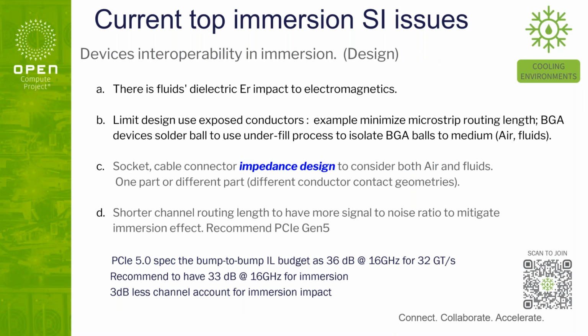This is also by design. We know that immersion has a dielectric constant impact, so impedance design is critical. One way is to tune the immersion impedance and interconnect impedance. Another way is to increase the signal-to-noise ratio, so we have less channel loss to compensate for the reflection loss caused by the liquid. For example, PCIe 5.0 currently requires 36 dB at 16 gigahertz for end-to-end margin. If we apply this rule, we could recommend 3 dB less end-to-end loss margin to compensate for the immersion impact.